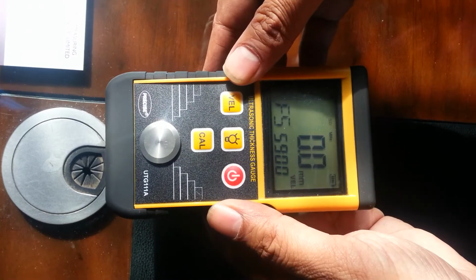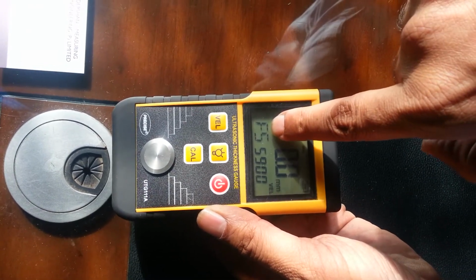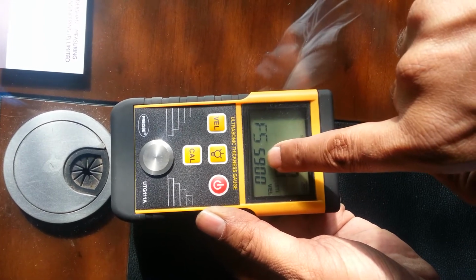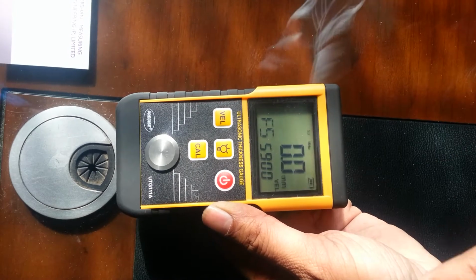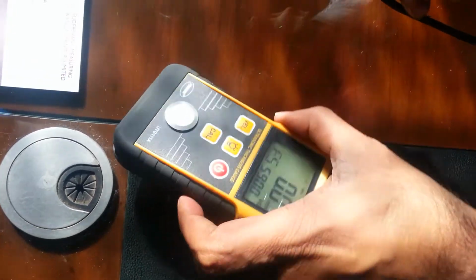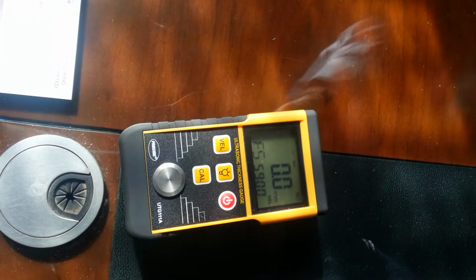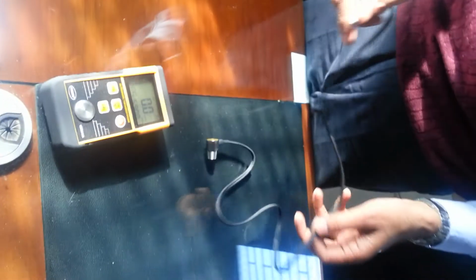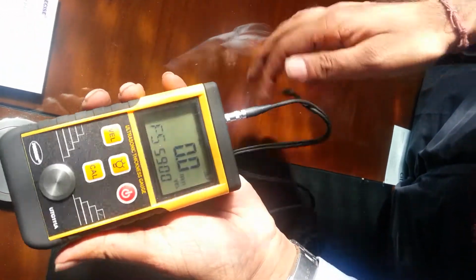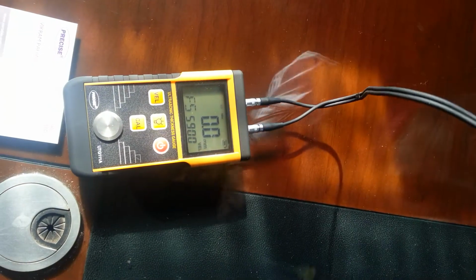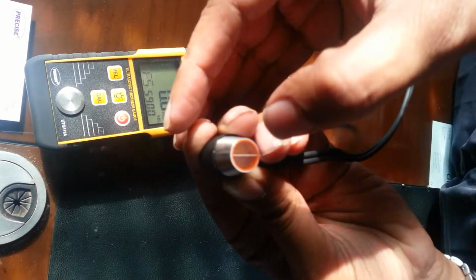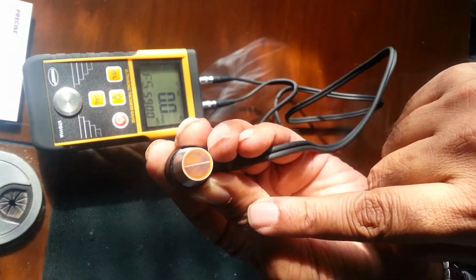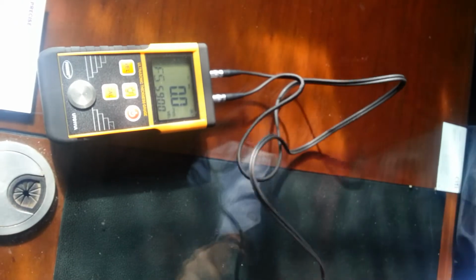This is the power button. We switch it on. Right now it says FS, which means ferrous, with speed of sound 5900, which is already fed in. We cannot change this. Now the first and foremost thing is calibration, which means we need to check whether this particular unit is giving the right reading or not. This is a cable through which we take the reading. This is a transducer and this is a crystal. So from one side the sound goes inside and from the other it comes back. We will use the gel, which is also called a coupling gel, to check.